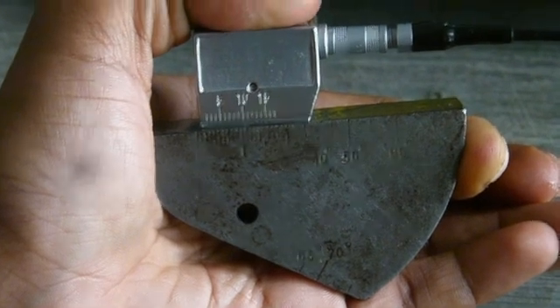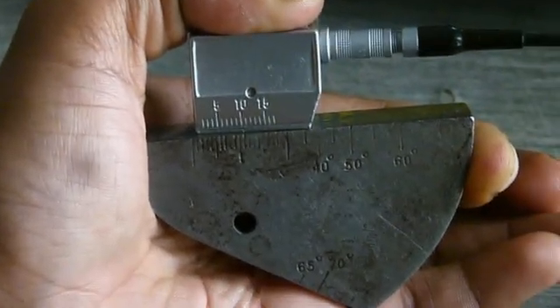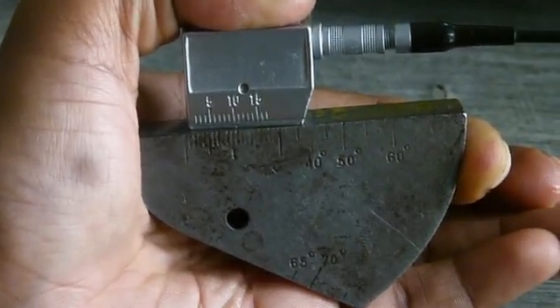This video is about construction of a DAC curve using an angled beam probe. The 100mm range is being calibrated using a V2 block.